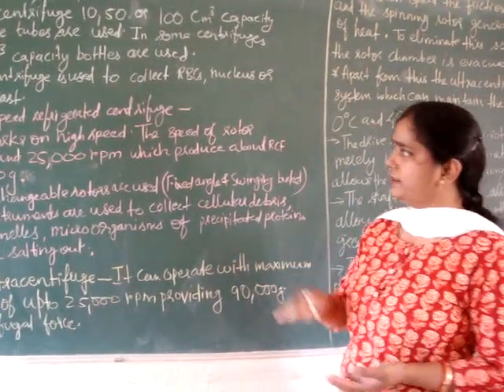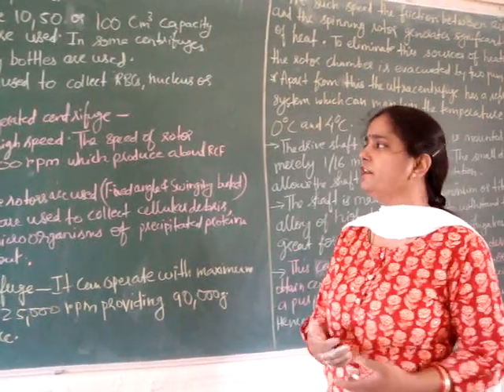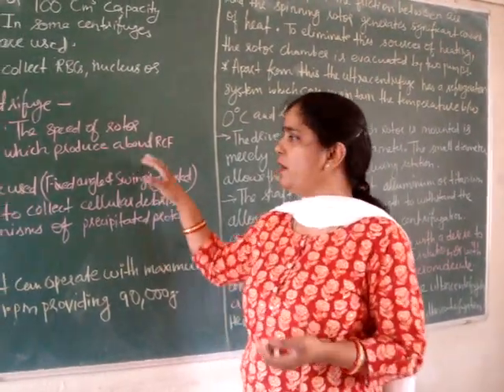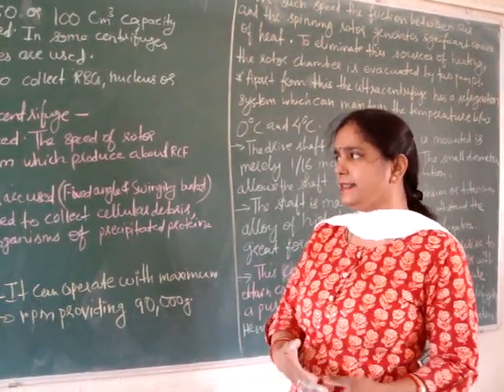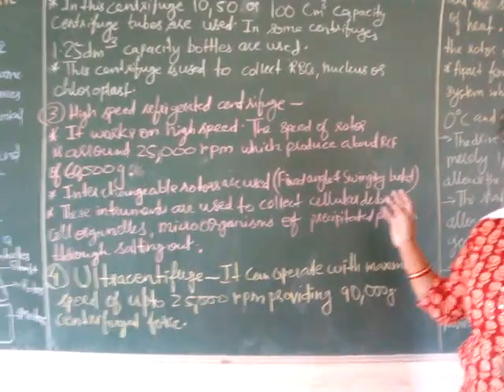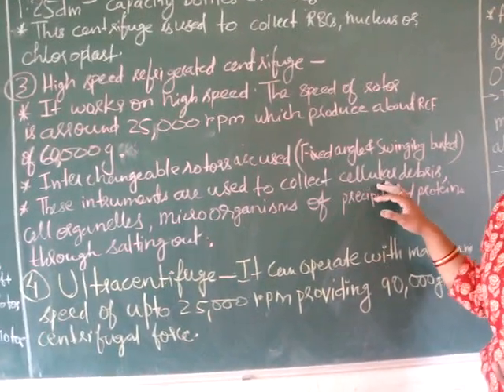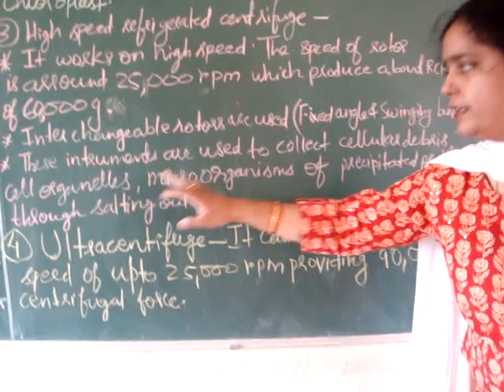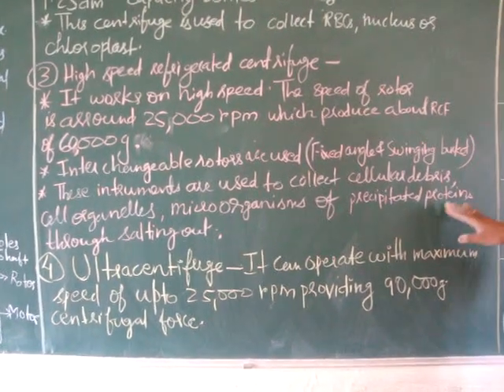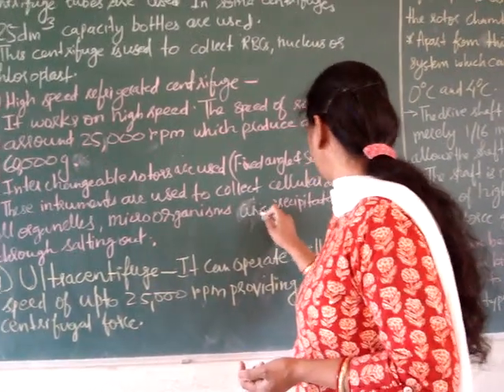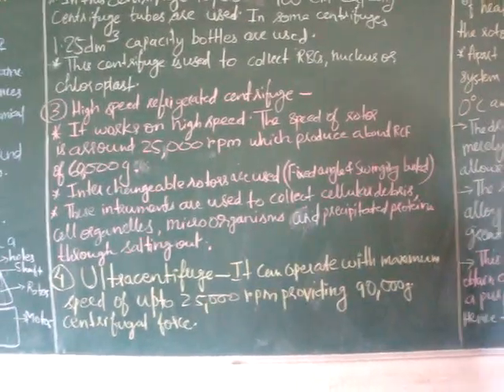The third type is the high speed refrigerated centrifuge. This centrifuge works at high speed — the speed of the rotor is around 25,000 RPM, which produces a relative centrifugal force (RCF) of about 60,000 G. Interchangeable rotors are used, including fixed angle and swinging bucket rotors. These instruments are used to collect cellular debris, cell organelles, microorganisms, and precipitated proteins through salting out processes.